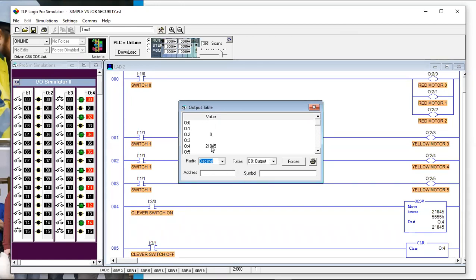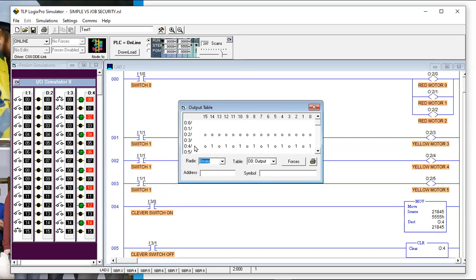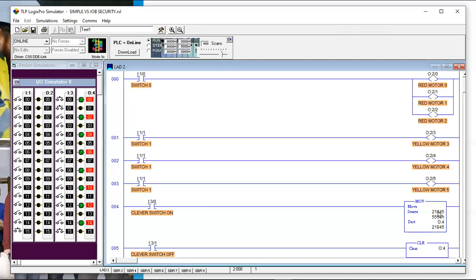He's sending this integer to a destination which happens to be the output file the card looks at. You can see all of a sudden it's not simple anymore — it's slick, it's efficient, it's clever. However, if somebody had to troubleshoot this and didn't understand what the program is doing, you're in trouble. The output you're looking for does not appear anywhere, and you can search for it all day long and it's never there. When you need to get equipment running and can't even find what output it's connected to — that's rough.